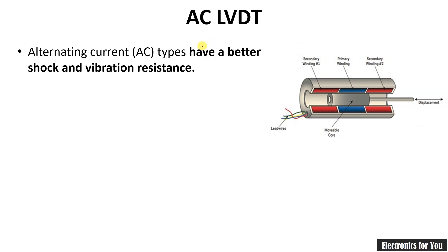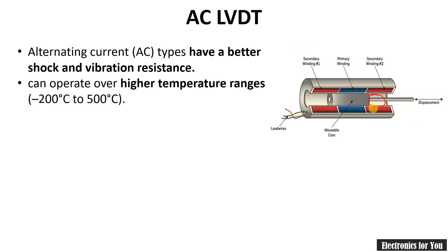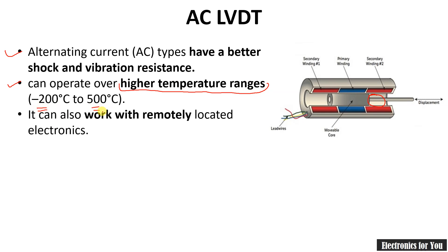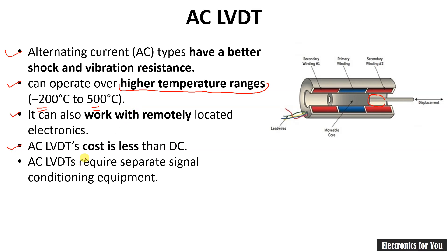Now let's see AC LVDT — the type based on output power. AC LVDT has better shock and vibration resistance. No electronic circuit is assembled on the LVDT itself for signal processing — such an LVDT is known as AC LVDT. It can be used for higher temperature ranges, from minus 200°C to 500°C, and can work with remotely located electronics. AC LVDT costs less than DC LVDT, but requires separate signal conditioning equipment placed outside the LVDT, which is its key limitation.